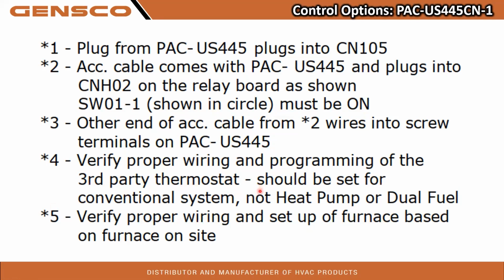When you're programming your 24-volt thermostat, make sure to set for conventional systems, not heat pump or dual fuel. This system is designed to operate as a gas furnace with an AC. So as far as the furnace is concerned, there's not a heat pump connected to it. It just thinks there's an AC and there's something calling it, telling it to turn the AC on. The heat pump is doing the rest of the work from there. So conventional system, gas furnace with AC, not heat pump or dual fuel.